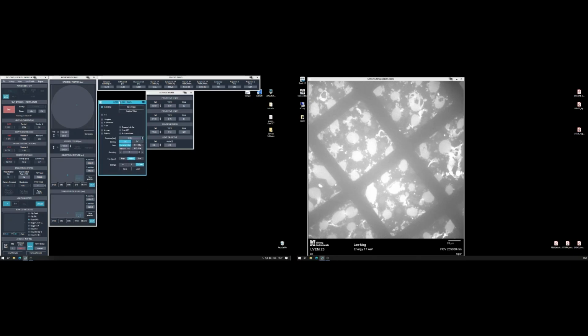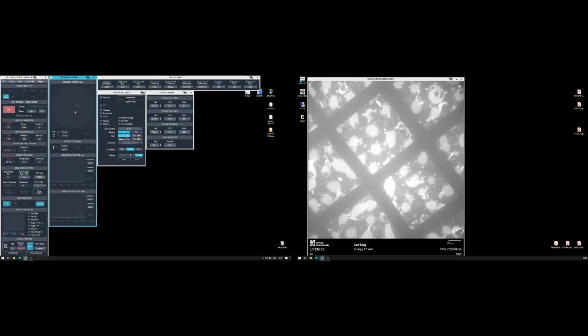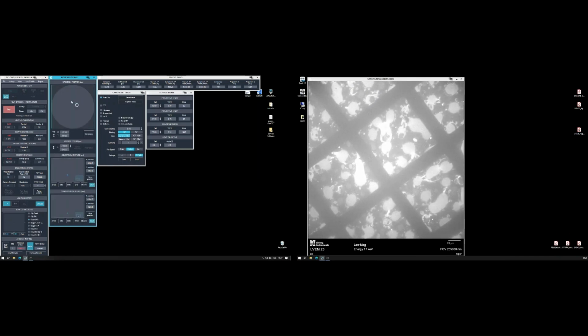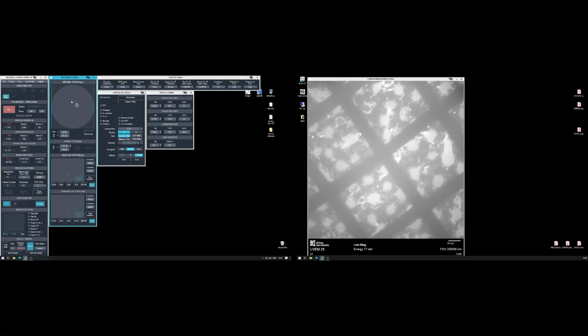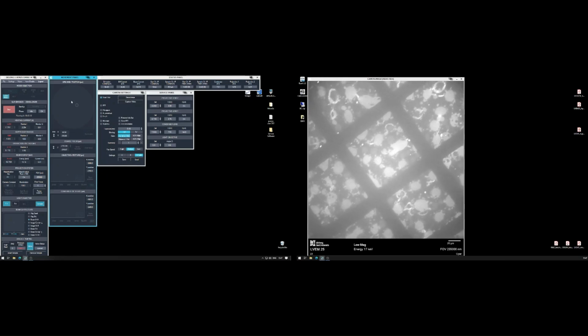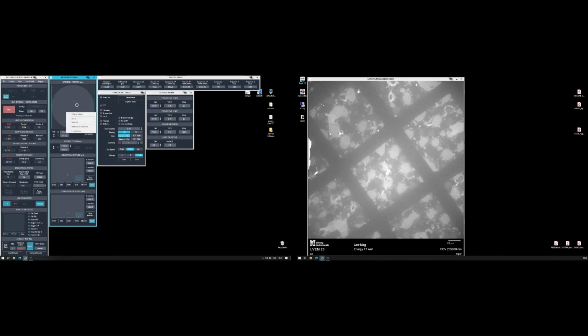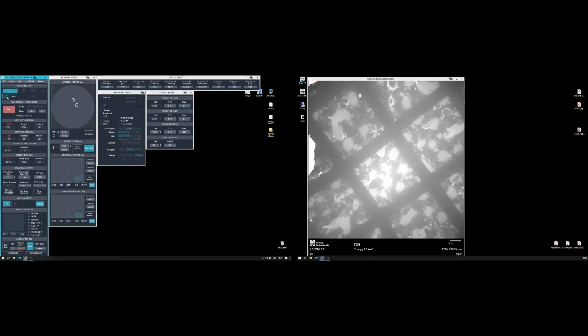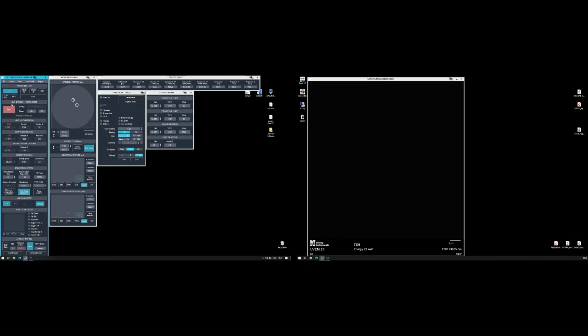It takes some time to set all important parameters, and here we are. We set the exposure time of the camera, and we can see approximately a quarter of the TEM grid, and we can easily find interesting places. We can store the places in the specimen window. And when we are fine, we can go back to TEM. Set again some exposure times and camera settings. We use the appropriate apertures, and we can immediately start imaging.